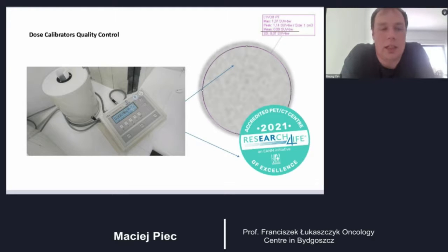Another issue that I'd like to address in my presentation is the dose calibrator. This is quite an important piece of equipment because dose calibrators help us identify the dose for a patient, and we find out using this calibrator whether the activity dose is the one that we would like to administer to him or her. So differences on those calibrators may also result in certain biases.